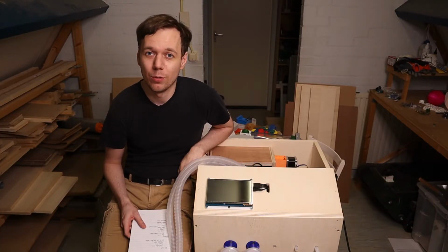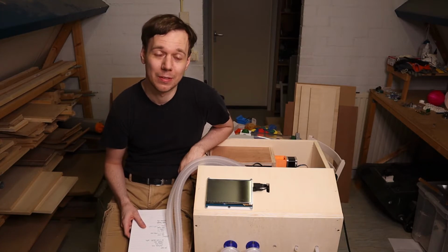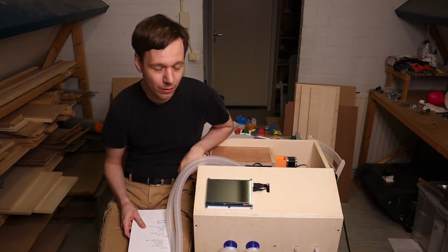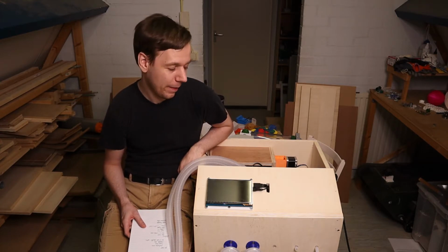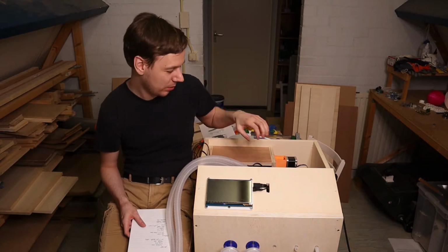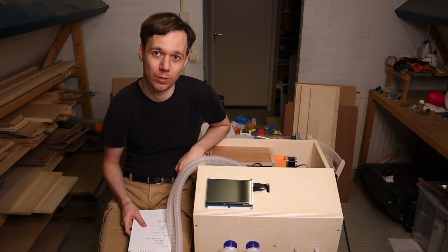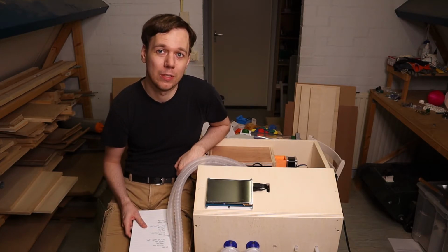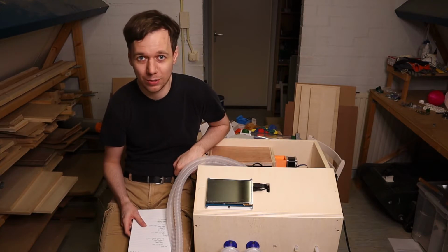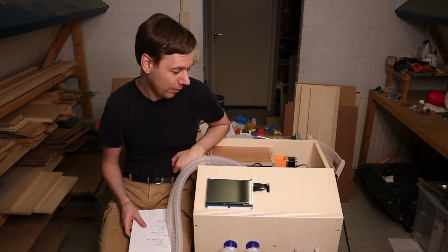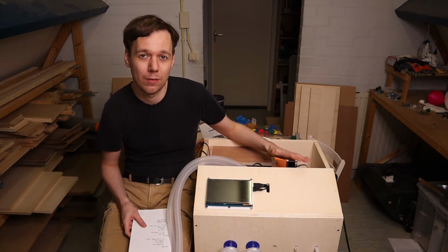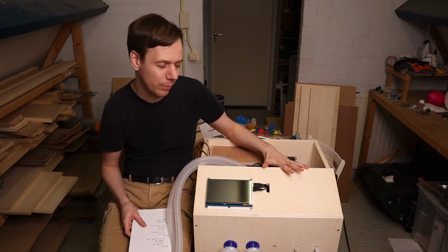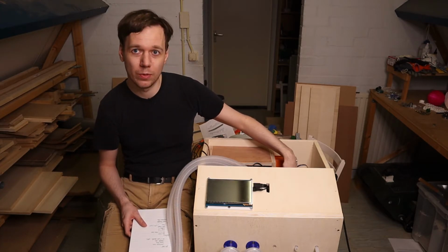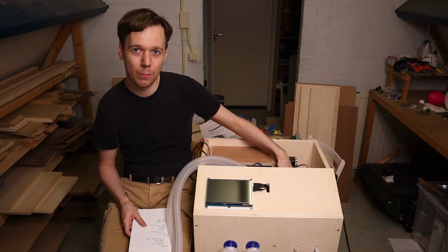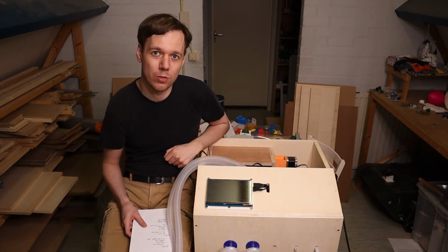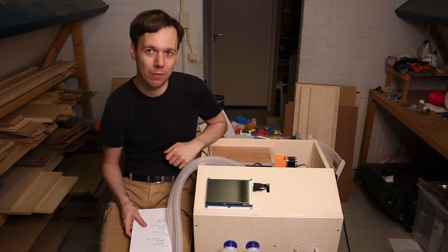Now that we've seen where the device is currently, let's go over the very long list of things that still need to happen to make it a viable device. The first thing I want to talk about is the oxygen input. So I've described how the oxygen and the air can be mixed inside of the bellows to provide the right oxygen concentration. But one of the things that's quite notably missing is a concentration sensor to verify that what you're asking for is what you're getting. The other thing is that the oxygen should be supplied at around atmospheric pressure, perhaps just a little bit higher. And you'd like to have a sensor on the input end where the oxygen and air meet at that T-piece, a pressure sensor to verify that the pressure is not outside of any limits.